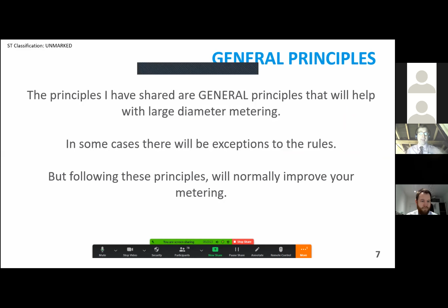So the first principle is that flow distortions travel further in larger mains than in smaller mains. If we look on the left-hand side here, in the ideal world scenario, we have water going down a main. Now, water goes at different velocities, at different speeds. In the ideal world, what we have in the middle of the main is the highest velocity, the quicker water. And then towards the edge of the main, because of the friction of the pipe wall, we have slower water, slower velocity. And this is what meters are designed for.